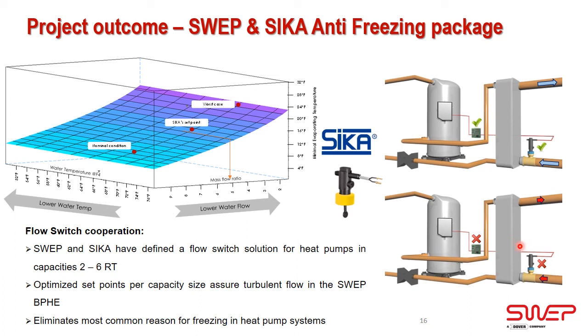Not all heat pumps in the US are being equipped with a flow sensor to avoid this. A flow switch is the most cost-efficient solution, but many are. And what we've seen is that the flow switch being used for this is typically one size fits all. So the same flow switch is used for a 1-ton and a 6-ton machine, and that's better than nothing. However, if you're using the same flow switch for a big capacity machine, you will be able to reach a very low mass flow before the flow switch stops the compressor.